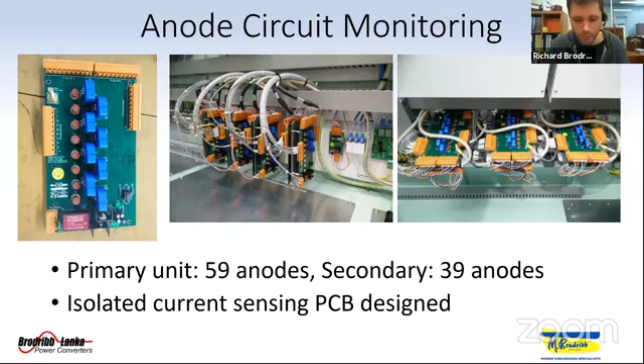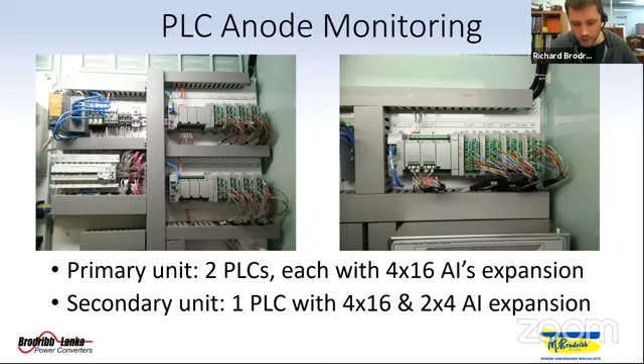In the primary unit, each of the signals monitored from the anode channels were wired to one or more PLCs, with each PLC fitted with multiple analog input modules. The primary unit had 2 PLCs, each fitted with 4x16 analog input expansion modules, and the secondary unit has 1 PLC fitted with 4x16 and 2x4 analog input expansion modules. The PLCs were chosen based on supplier and manufacturer recommendations for minimizing costs during manufacturing, operation, servicing, and life of equipment. The HMI panel displayed all of the anode currents and their cross-bond current.